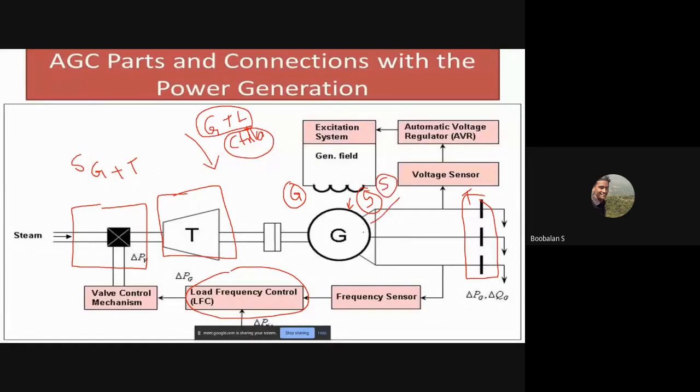We are now interested in visualizing these things, and in finding out these changes. We'll see later. The main thing here is the synchronization coefficient. Delta is called the load angle or torque angle. It is maintained as a constant for a synchronous generator. But if the load is changed or a short circuit fault occurs, definitely the load angle or torque angle of this synchronous machine is going to change. It definitely changes, but with the help of the controller's effort, it is maintained as constant. This we are going to see.